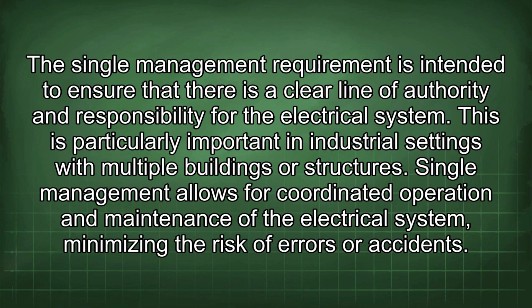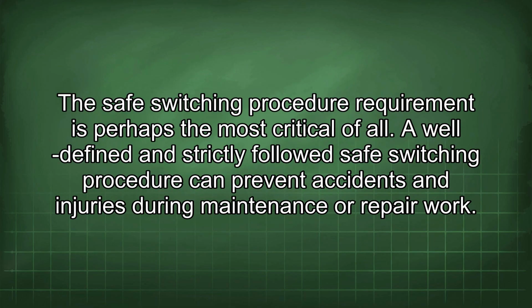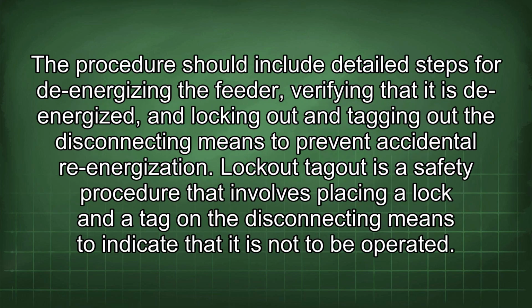The single management requirement is intended to ensure that there is a clear line of authority and responsibility for the electrical system. This is particularly important in industrial settings with multiple buildings or structures. Single management allows for coordinated operation and maintenance of the electrical system, minimizing the risk of errors or accidents. The safe switching procedure requirement is perhaps the most critical of all. A well-defined and strictly followed safe switching procedure can prevent accidents and injuries during maintenance or repair work. The procedure should include detailed steps for de-energizing the feeder, verifying that it is de-energized, and locking out and tagging out the disconnecting means to prevent accidental re-energization.